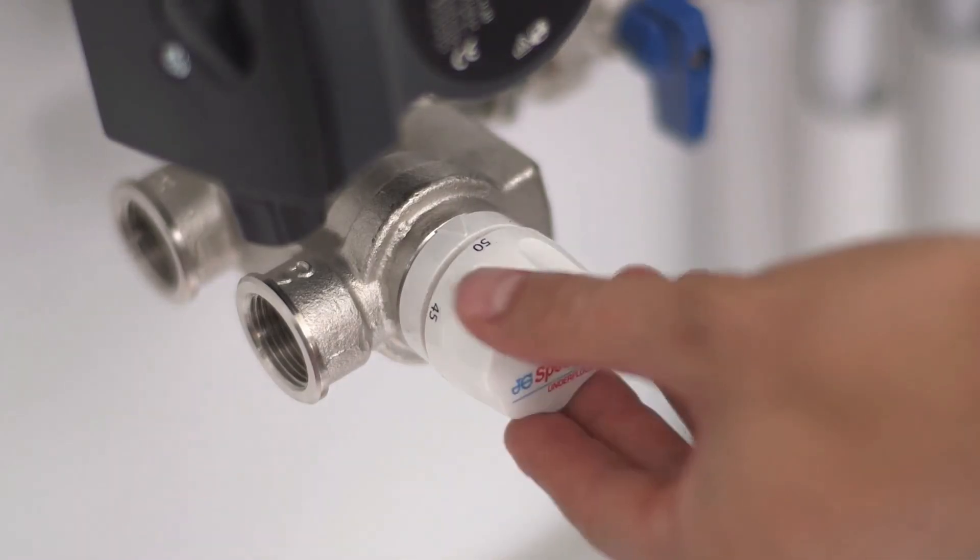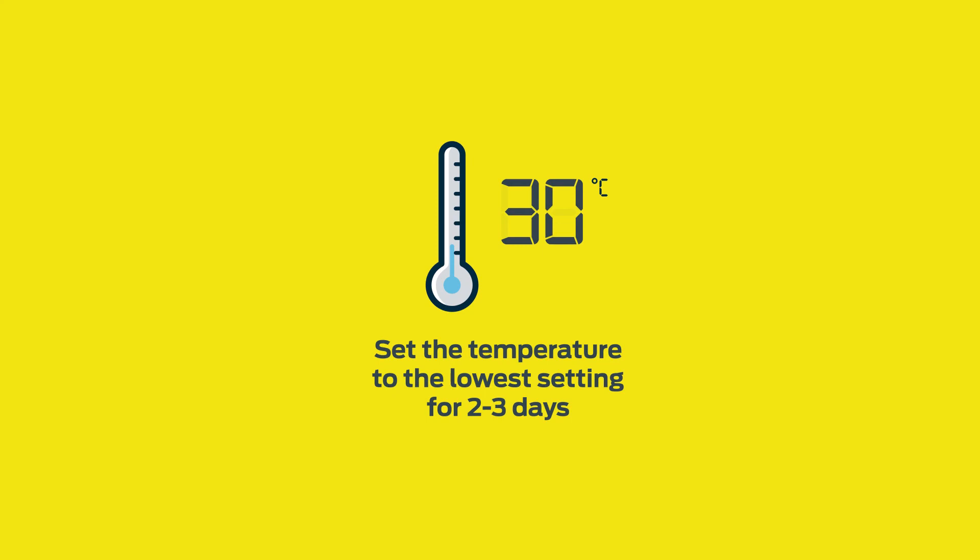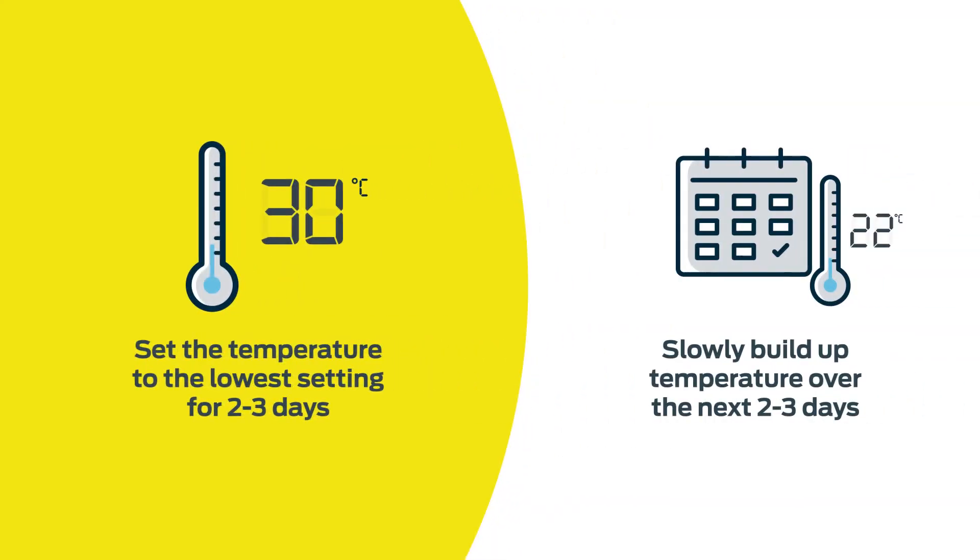When turning on initially, the temperature of the blending valve should be set to the lowest setting, 25 to 30 degrees, and run for 2 to 3 days before building up the temperature over the next couple of days.